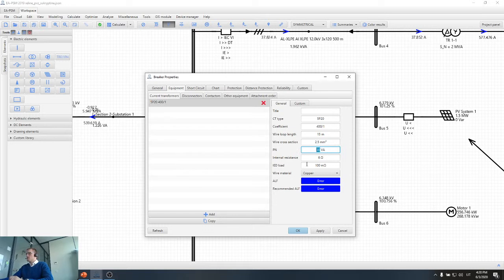Transformer power, let's assume that it's, let's say, 15 volt amps, because we'll connect only single relay, so we don't need a very powerful transformer. Then internal resistance. As a rule of thumb, this internal resistance is something from 4 to 6 ohms. Actually now it's 6 ohms provided here by default, and I will leave this default value. And here is relay load. Basically this is the resistance of the relay, so it's 100 milliohms. So I will leave this value.